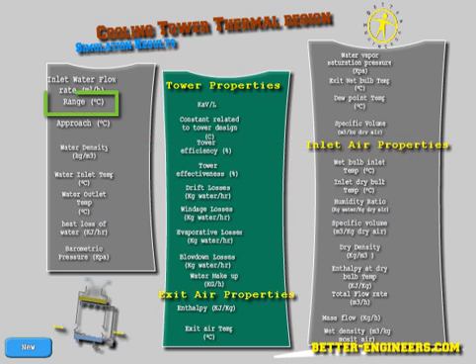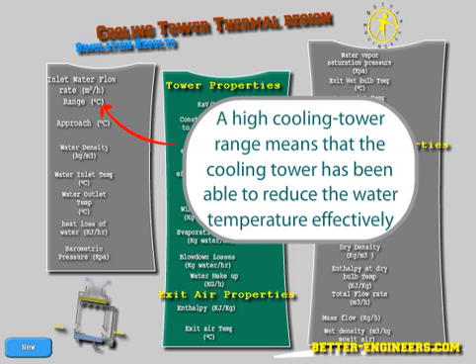If you have any questions, please contact us at info@better-engineers.com. The range is a common unit used in cooling tower sizing, which is basically the difference between the hot water temperature and the cold water temperature. A high cooling tower range means that the cooling tower has been able to reduce the water temperature effectively.